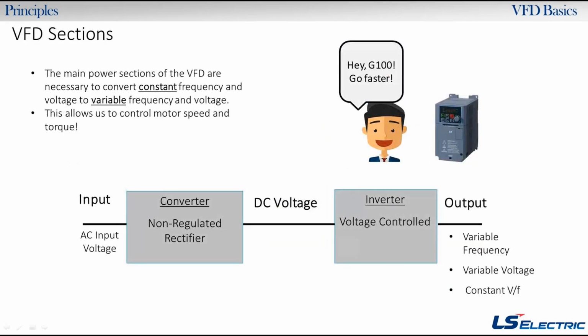Okay, so this is the main topics we're going to be talking about, which is what's happening inside of a drive. There are really three main power sections in a VFD: the converter section, the DC bus section, and the inverter section. A lot of people just call a drive an inverter, as some of you maybe hear, but inverter is just slang for the back end of the drive.